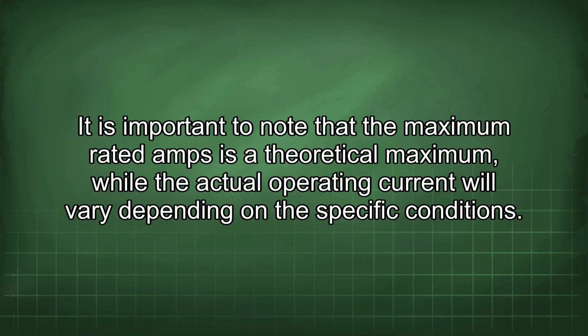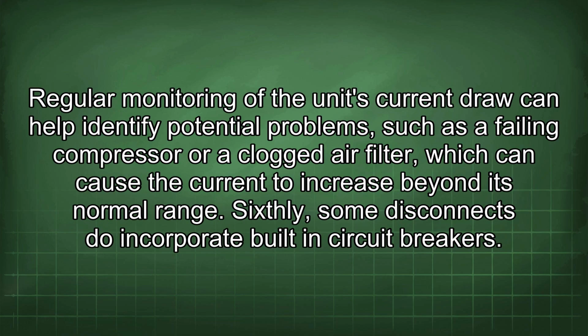It is important to note that the maximum rated amps is a theoretical maximum, while the actual operating current will vary depending on the specific conditions. Regular monitoring of the unit's current draw can help identify potential problems, such as a failing compressor or a clogged air filter, which can cause the current to increase beyond its normal range.